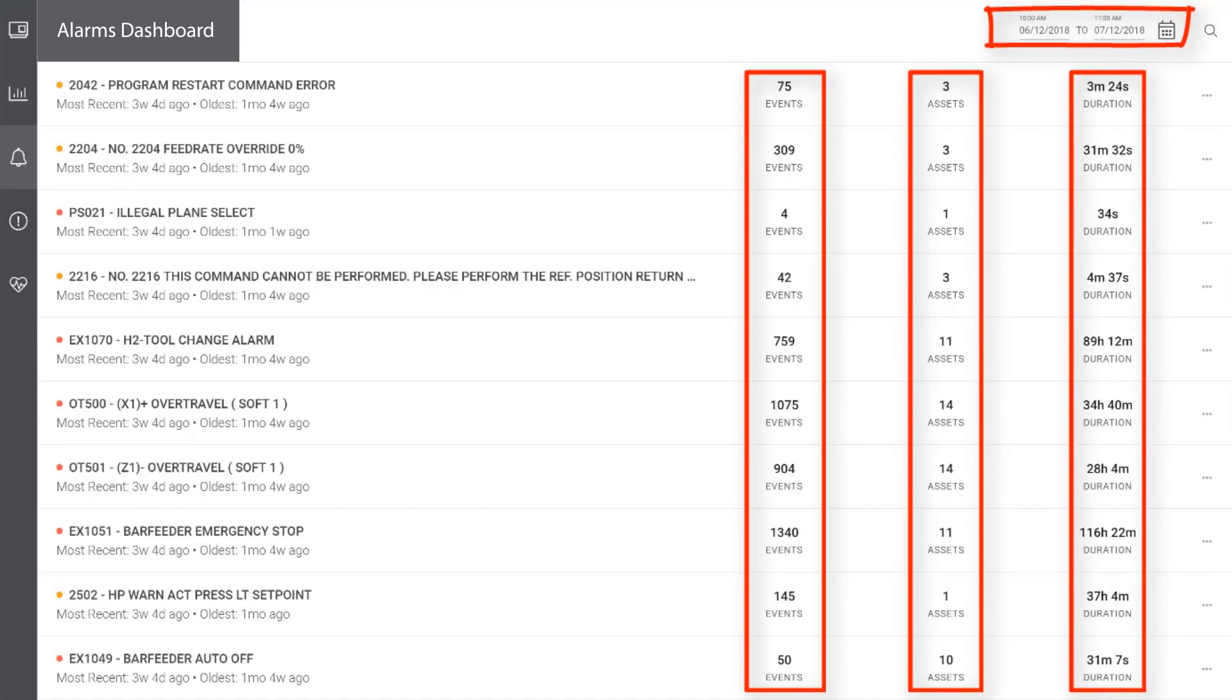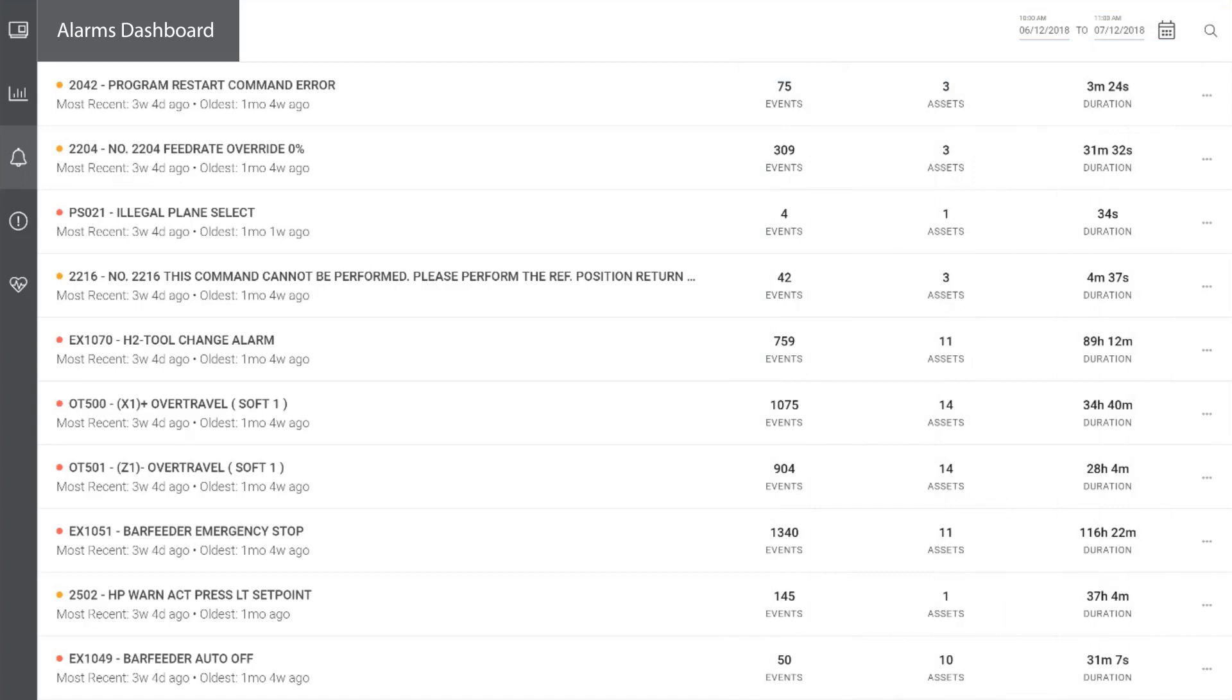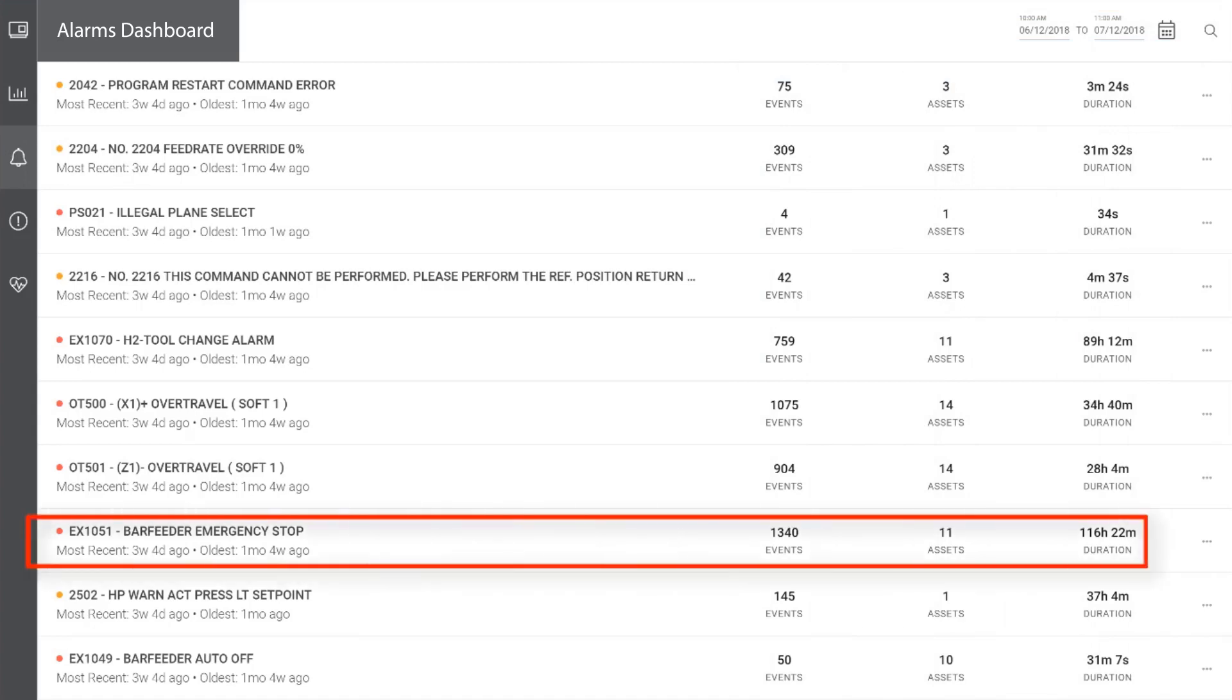To direct improvement efforts, a good place to start is analyzing an alarm that has numerous events, impacts several assets, and has caused significant downtime. For our example today, we will be analyzing the bar feeder emergency stop error because it meets all of the criteria. It has 1340 events in the past month, is impacting 11 assets, and has caused 116 hours of downtime over the course of the month.